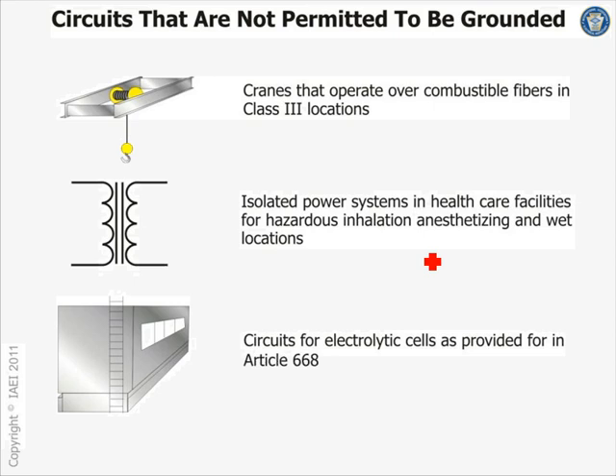Isolated power system in health care use. Just as open, you're sitting on the machine and they're working on you, and you're powering that equipment. That's the power that powers the equipment when your chest is open, it shall not be grounded. Isolated power system in healthcare facilities, hazardous inhalation anesthesia locations, all these you shall not do that. That's an ungrounded system that they run there. Electrolysis, high-tech, I don't know, I haven't dealt with that. These also cannot be grounded.